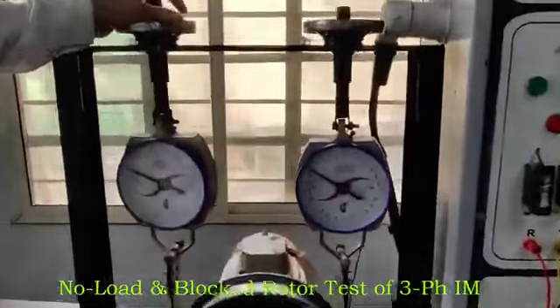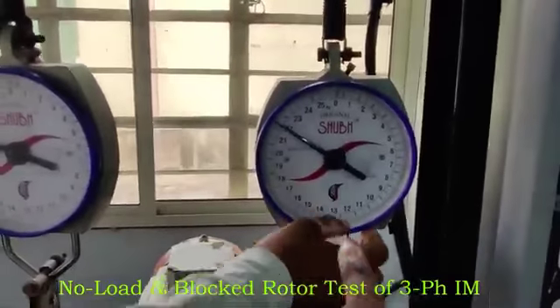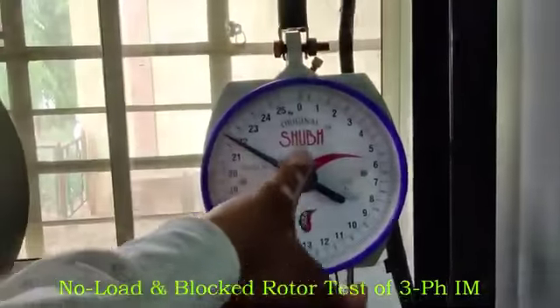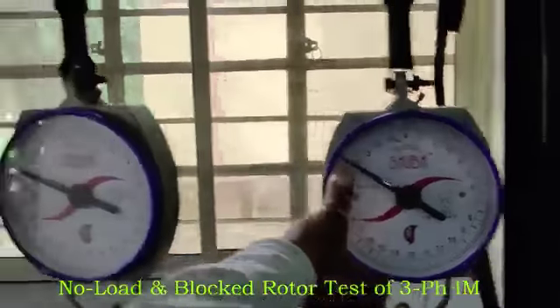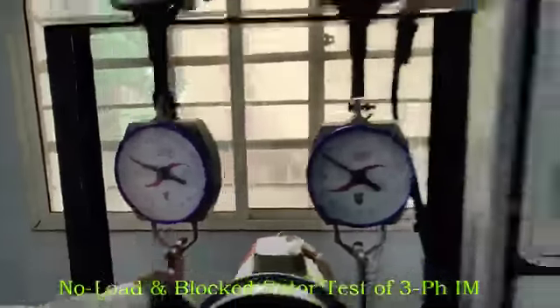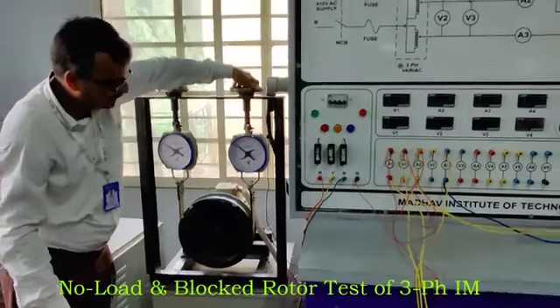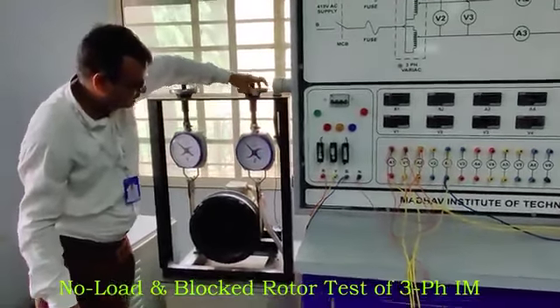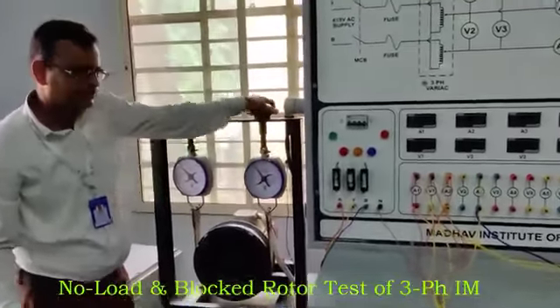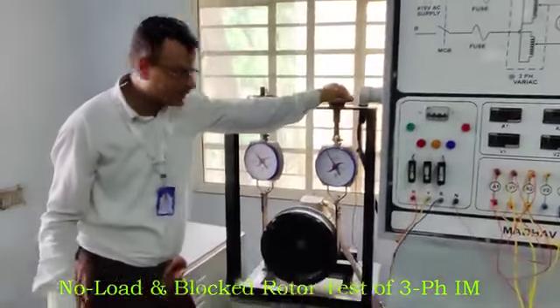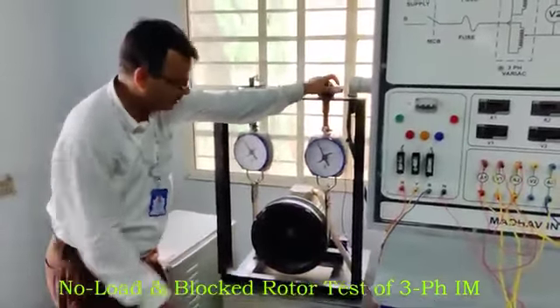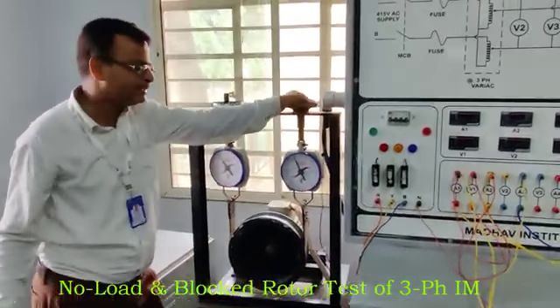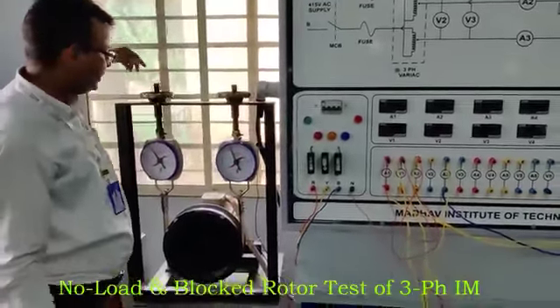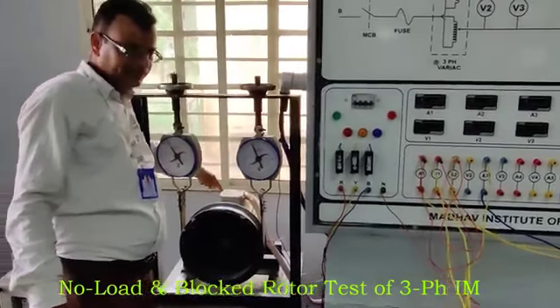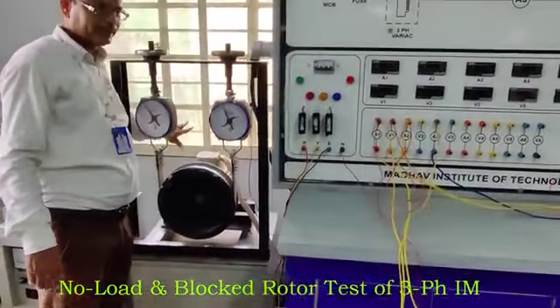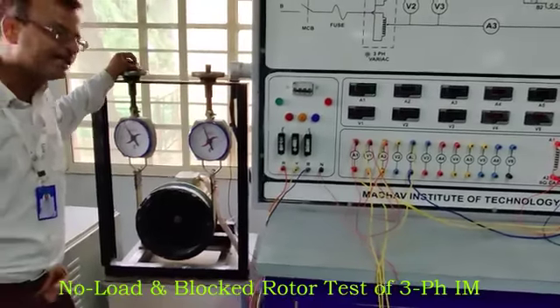Second thing, it is blocked, and the load here is not at 0 position. It is 22 kg here and 21, so it is totally blocked. Second thing, we have already learned in the theory part that this test is performed at the rated current. The rated current of this particular machine is 5 ampere, as given on the nameplate rating of this machine. The machine rating is 5 HP, 5 ampere and 450. This test is performed at the rated current.